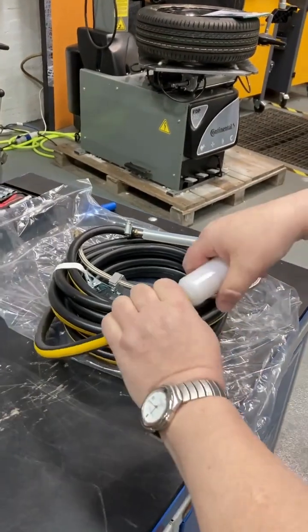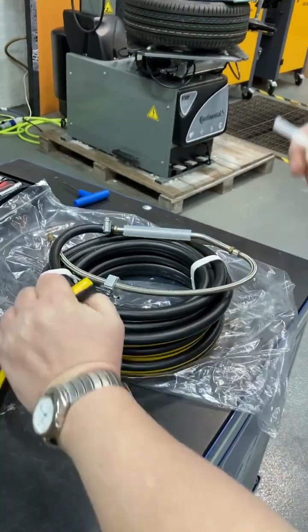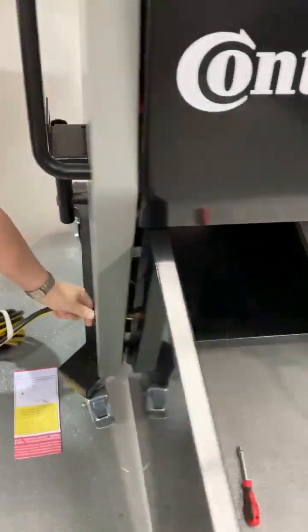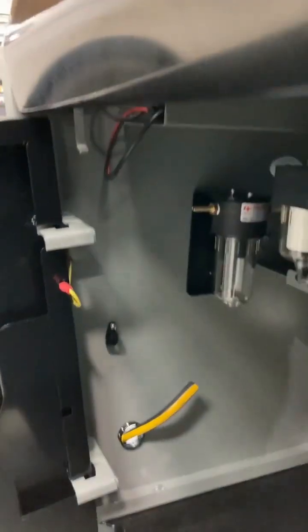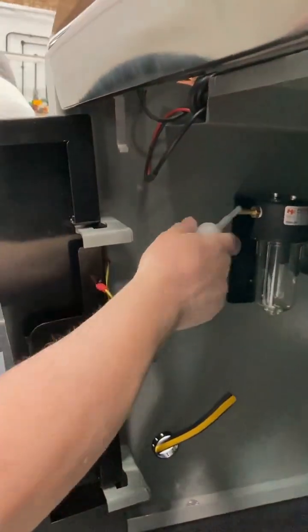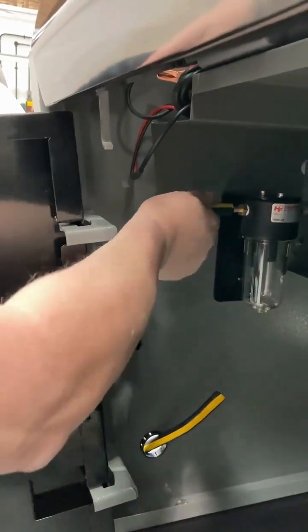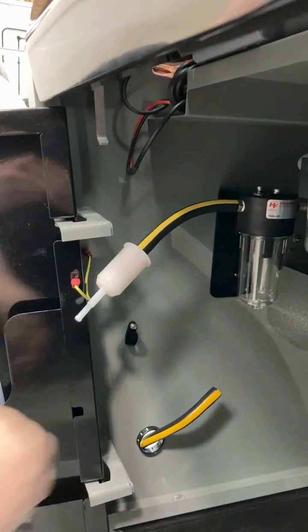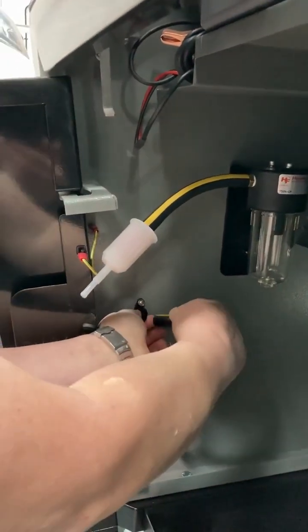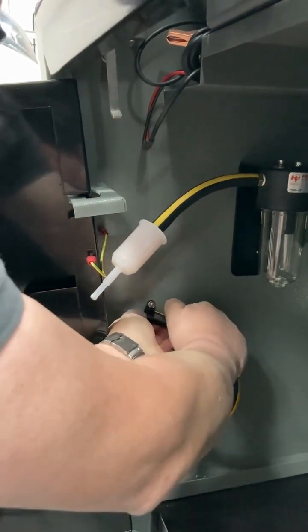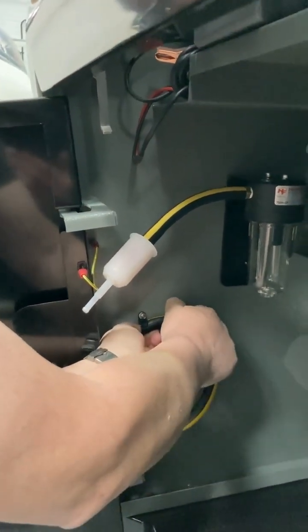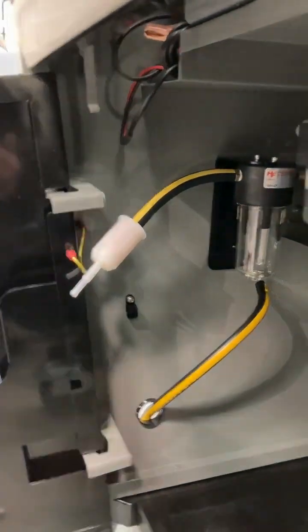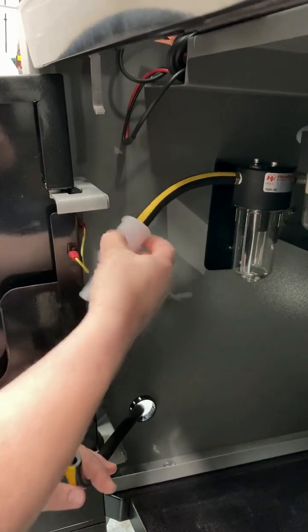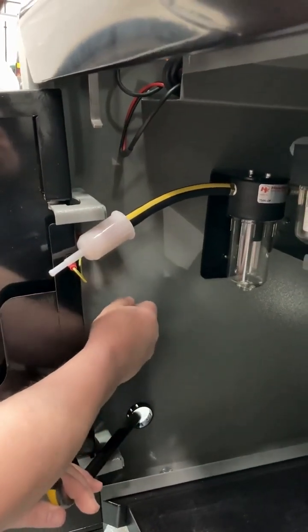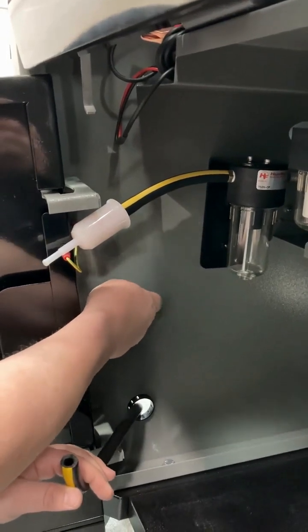To fit the gas sample probe, grab the filter, split the sample probe from the pipe. Sample probe then pushes through the side of the unit. This part connects onto the brass connector for the water trap. The hose feeds through the P-clip. So, with the pipe fed through and the filter attached, remove the P-clip, which is a 7mm nut.